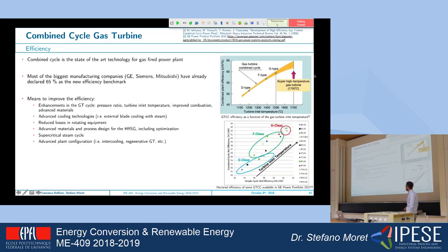So as I told you last time, roughly the efficiency of a gas turbine is in the range of 30 to 45%, and we can take a value of 42 as reference. The efficiency of a steam cycle can usually get up to 45% or so. When we combine the two, using the formula above, we obtain the efficiency of a combined cycle, which is today, if I'm not wrong, the highest efficiency ever reached by a combined cycle. I think every now and then they have this Guinness Award for the best combined cycle ever. I think the last time was Siemens obtaining it for a 63% cycle.